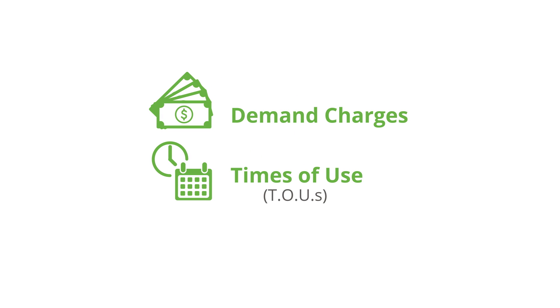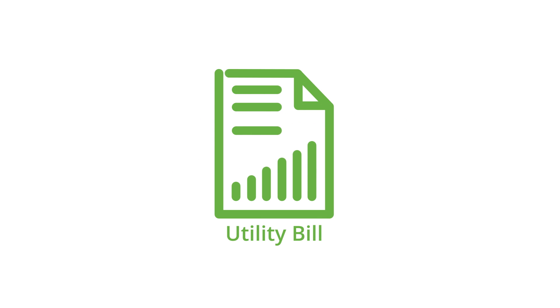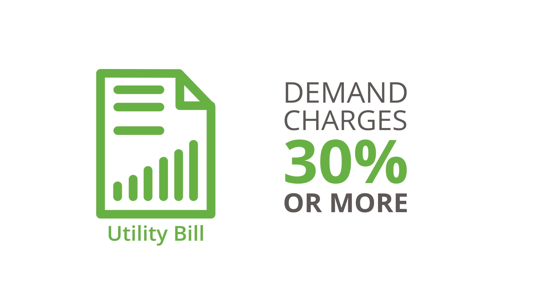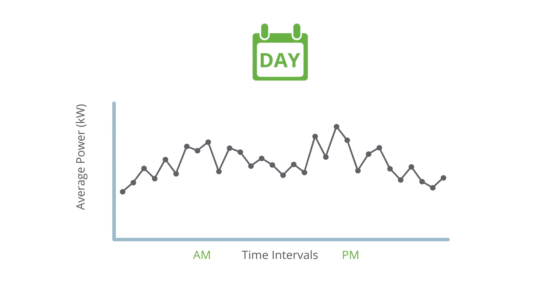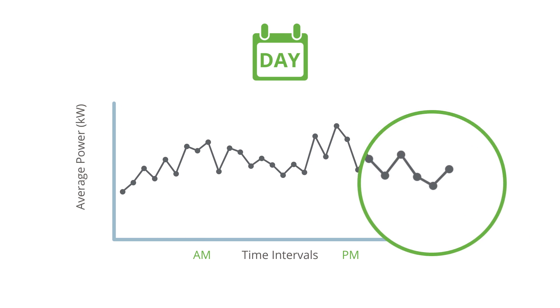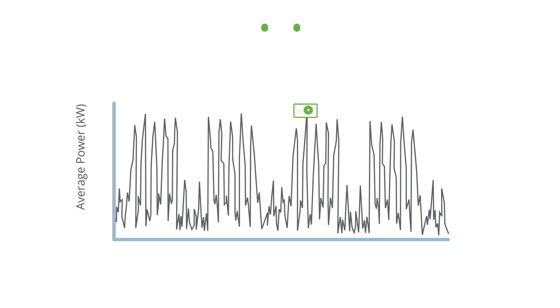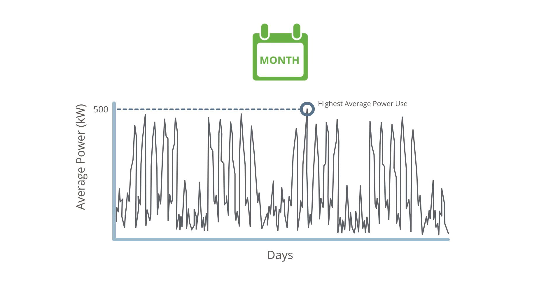To illustrate how Sunvault DX storage saves money by reducing energy costs, we should first explain utility demand charges and times of use. Demand charges are fees utilities charge commercial customers on top of regular energy costs. They're often 30% or more of an organization's utility bill, and the utility calculates them by looking at all days within a billing cycle and then averaging power usage in what are usually 15-minute time intervals. The highest average power usage within a billing cycle determines the all-hours demand charge.